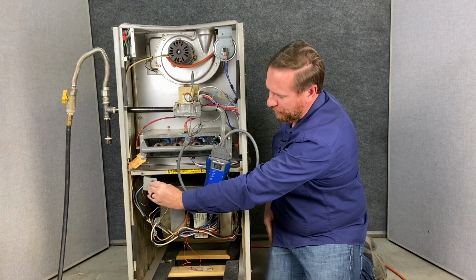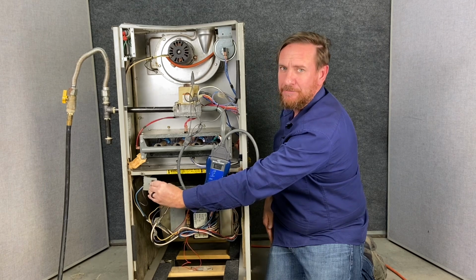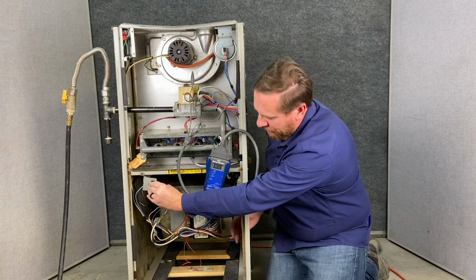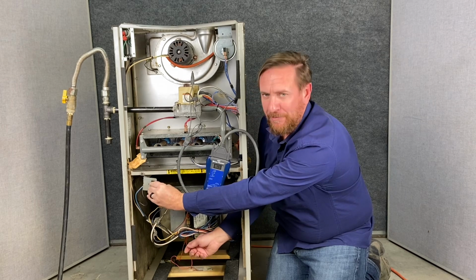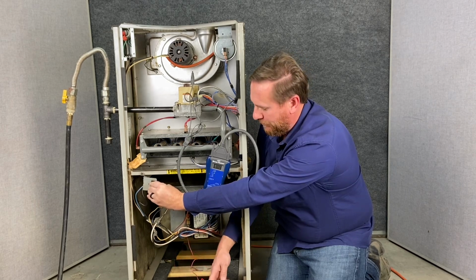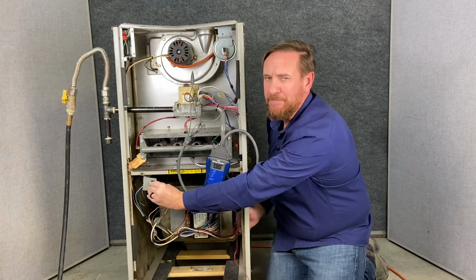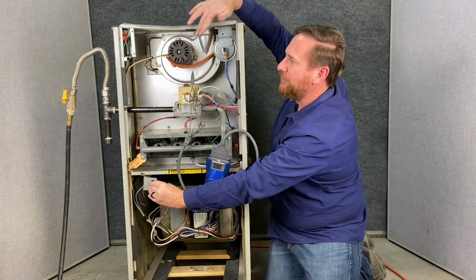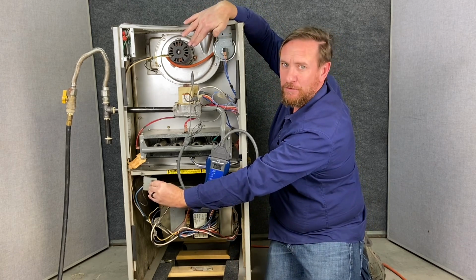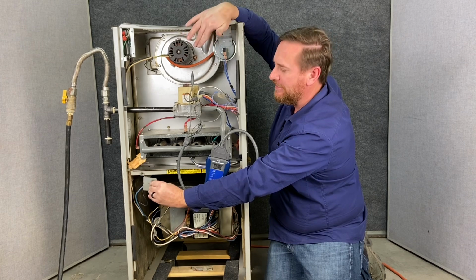IFC should bring the blower on, which is quite unusual. It should have already kicked on by now. We're going to go ahead and end our call for heat, so I'm just going to pull my jumper off. Pull the jumper off, notice that the flames immediately shut off. But this inducer fan motor kept running for just a little while to post-purge, to clean out the heat exchanger.